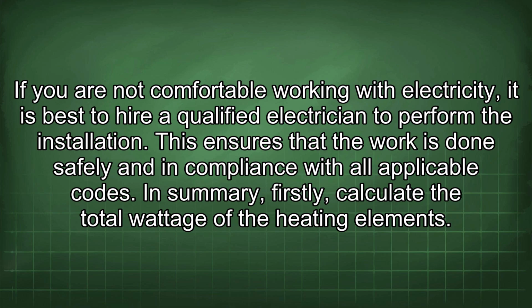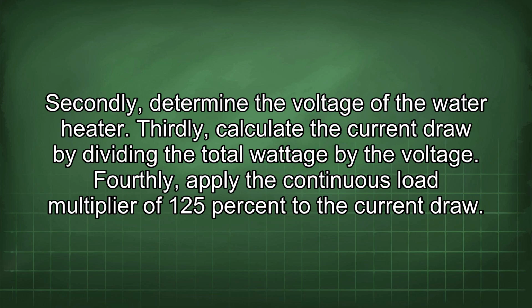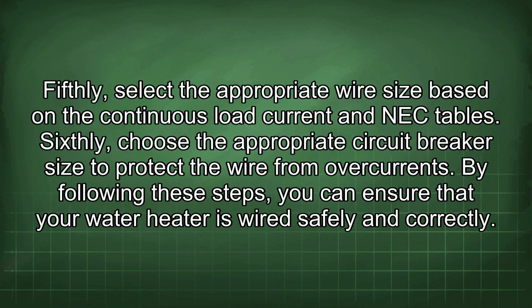In summary, firstly, calculate the total wattage of the heating elements. Secondly, determine the voltage of the water heater. Thirdly, calculate the current draw by dividing the total wattage by the voltage. Fourthly, apply the continuous load multiplier of 125% to the current draw. Fifthly, select the appropriate wire size based on the continuous load current and NEC tables. Sixthly, choose the appropriate circuit breaker size to protect the wire from overcurrents. By following these steps, you can ensure that your water heater is wired safely and correctly.